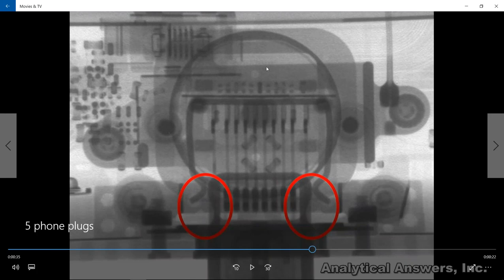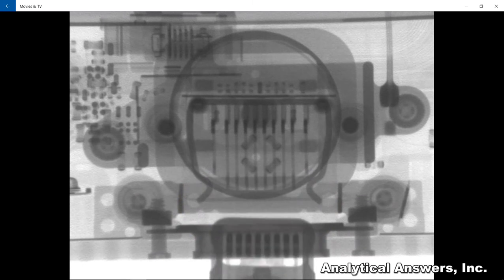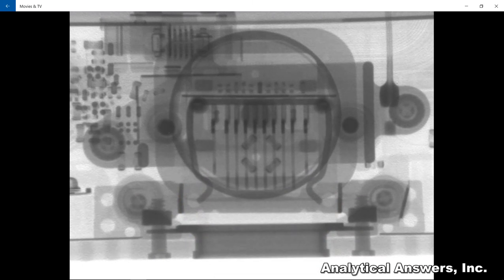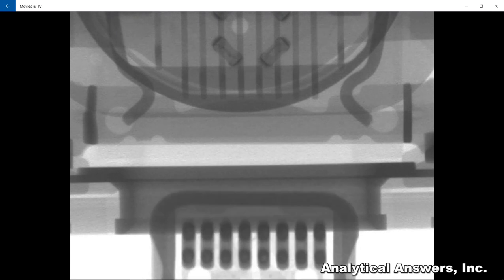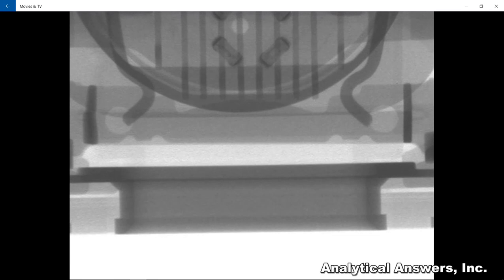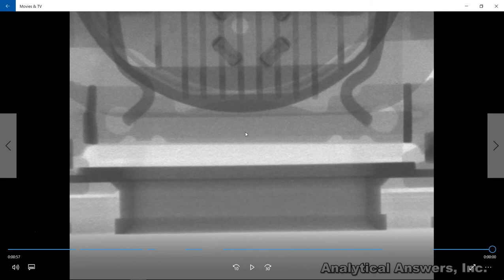On this one which is the suspect the third party, we can see that the cable is not able to go all the way in and securely engage these clamps from the side which are inside the power plug. Here when we start to apply tension it kind of more dribbles out as opposed to flying out because this hold was much weaker than what you could see on the control unit. What it turns out is there was a piece of plastic which doesn't show up well in the X-ray when you're trying to penetrate a bunch of metal, that was actually preventing that cable from securely entering all the way into the socket.